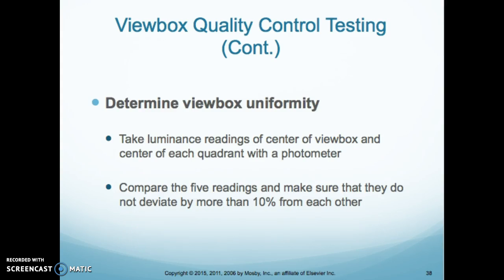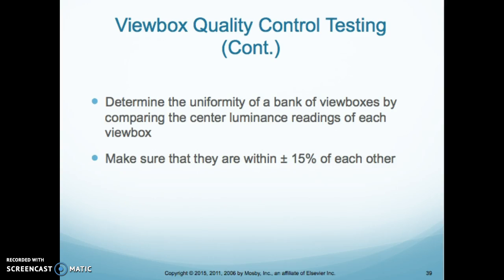When we're looking for uniformity within the view box, we take the luminance reading at the center of the view box and center of each quadrant with the photometer. We compare the five readings and make sure that they do not deviate by more than 10% from each other. To determine the uniformity of a bank of view boxes, we compare the center luminance reading of each view box and make sure they're within 15% of each other.